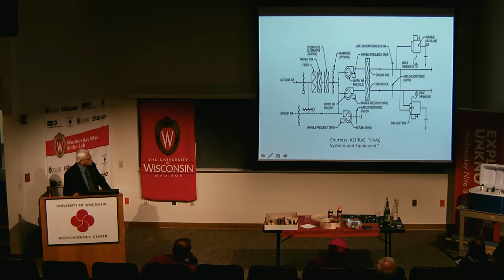So in the cooling season, this is pretty much shut off, and the cold air comes into the zone. There is a direct digital controller which sets the set point for the flow, and that's how the mixing takes place. Now here are the dampers, one for exhaust, one for outdoor ventilation air, one for return air mixing with the outdoor ventilation air. Now you can see the potential for fault.